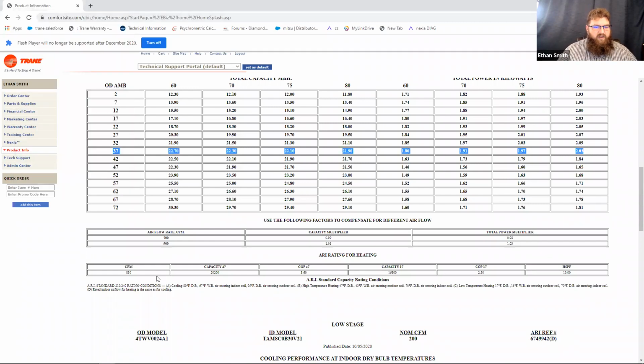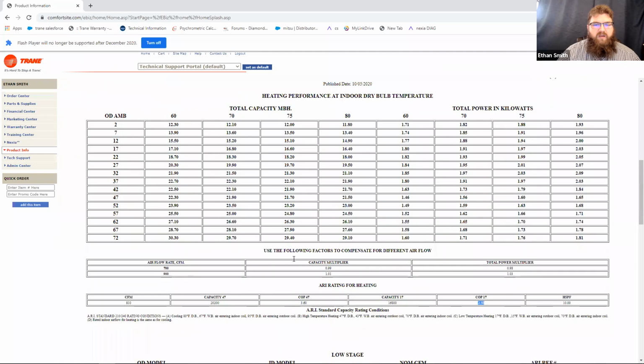Now, AHRI does go out and give you some arbitrary numbers. So down here you see it says capacity 47 and COP 47. So that's already calculating your COPs at 47 degrees. But you notice how it's higher at 47 degrees than it was at 37 degrees. So the COP changes based on your conditions. Okay. They also give us a COP at 17 down there as well. So the COP at 17 is 2.5. So generally, as outdoor ambient goes down, your COP is going to go down because the unit becomes less efficient. Okay.